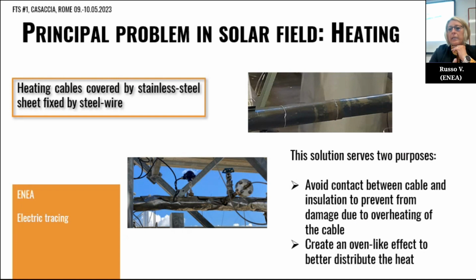Here we have another picture of an installation along the piping. Generally, the cable must be covered by a stainless steel sheet. This solution avoids contact between the cable and the insulation, in order to prevent damage from overheating of the cable itself. And also in order to create an oven-like effect to better distribute the heat along the pipe or along the component.